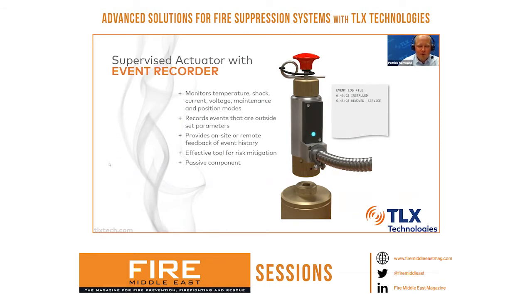And for the events that are recorded, we can set specific parameters. So if the current goes above 200 milliamps, that's an event. We can set those parameters to whatever the customer wants for the device and create that log. When we create that log, that data can be either stored locally on the device, with a mini USB to pull it off and review the log data, or we also have the ability to send that data remotely through a Wi-Fi connection or some sort of wireless protocol.